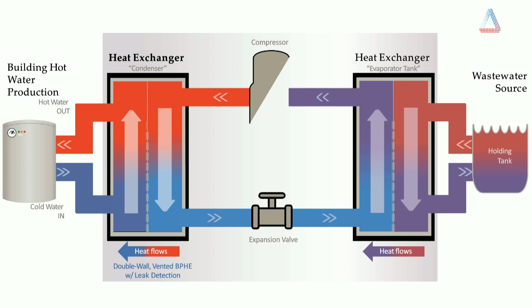Now, some of the cool things we've done with the Piranha unit is we can add an extra heat exchanger. The reason we add this extra heat exchanger is you can also use this unit to extract heat from a building or multiple buildings. And if you extract heat from a building, you're basically providing cooling, right? So you can do that, or you can use that to temper, and this crowd is going to resonate with you, or retro-commission a ground heat exchanger that may have been installed years ago. They changed the load so the temperature's creeping up or it's creeping down. We can condition that loop.